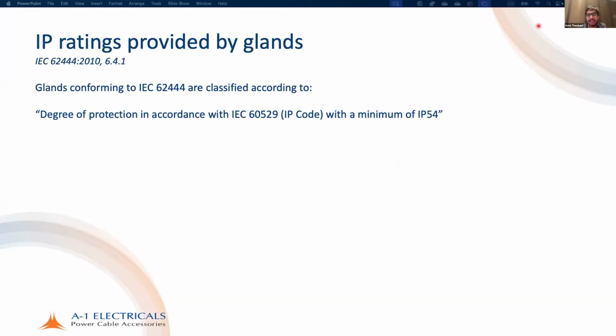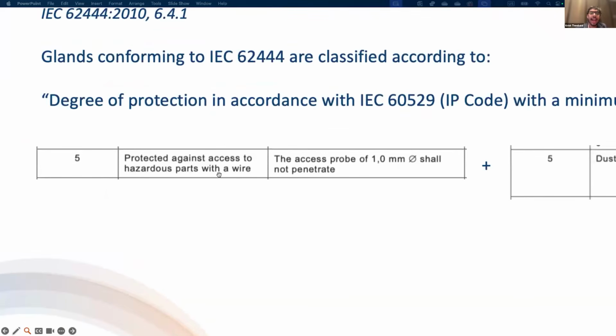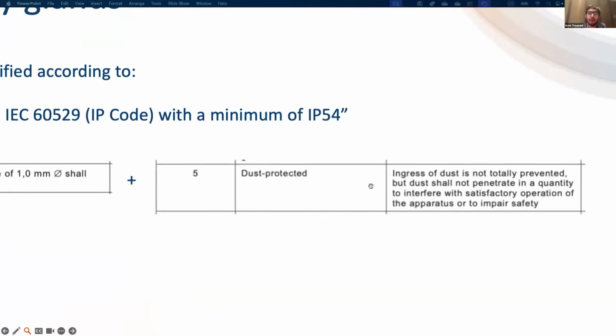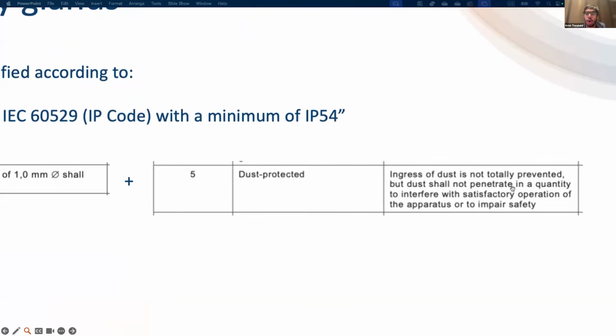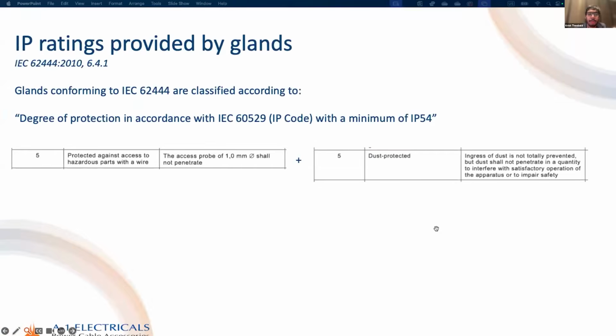When we talk about glands that provide this IP rating, what does it mean? If the gland conforms to IEC 62444, it is required to be classified according to its IP code, and the minimum is IP54. So what does that mean? Protection against access to a hazardous part with a wire. An access probe of 1 millimeter shall not penetrate, and it is dust protected. Ingress of dust is not totally prevented, but dust shall not penetrate in a quantity that interferes with satisfactory operation of the apparatus or impairs safety.